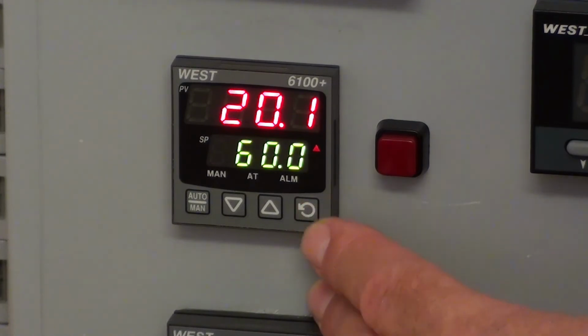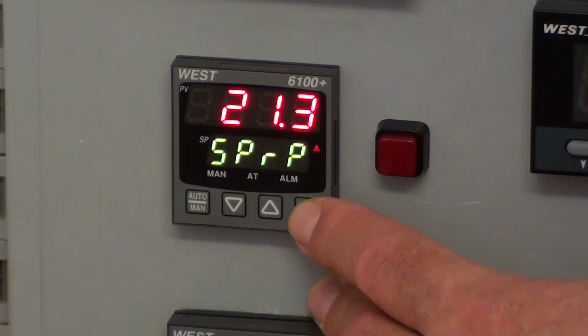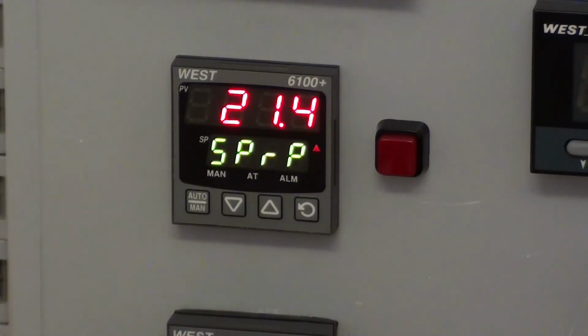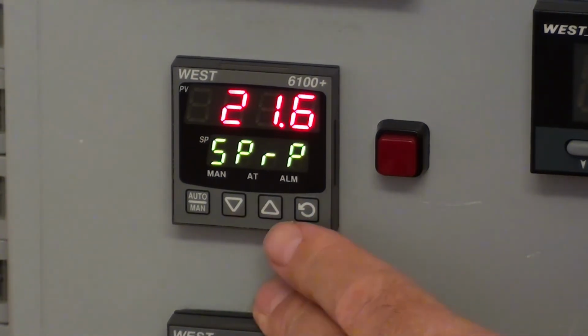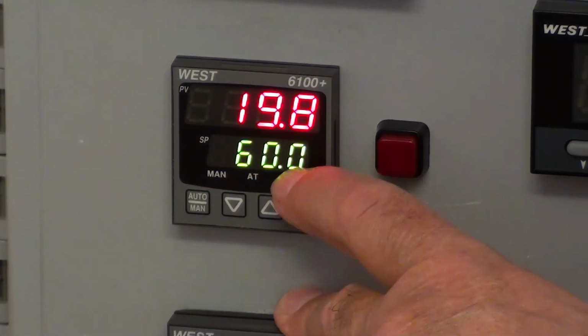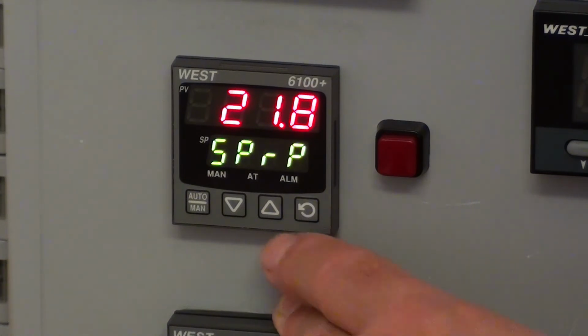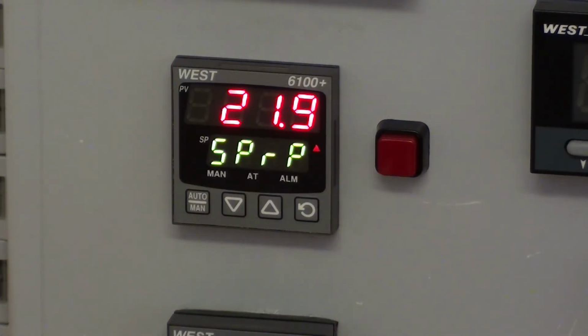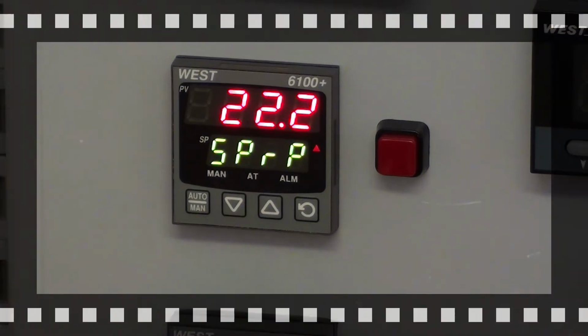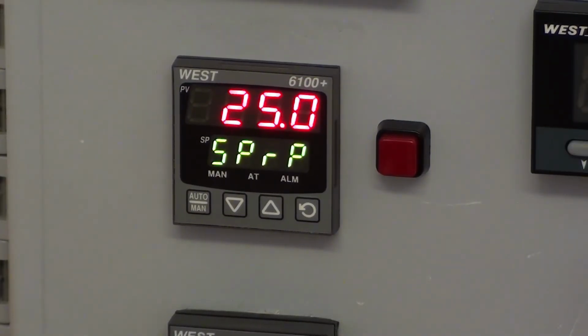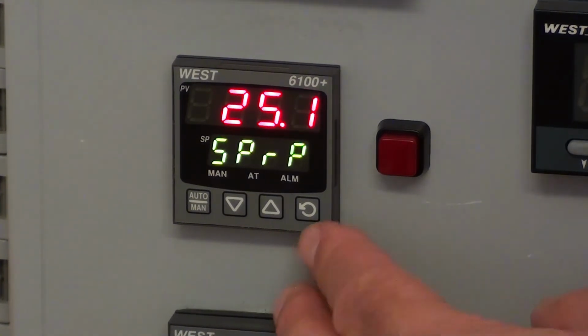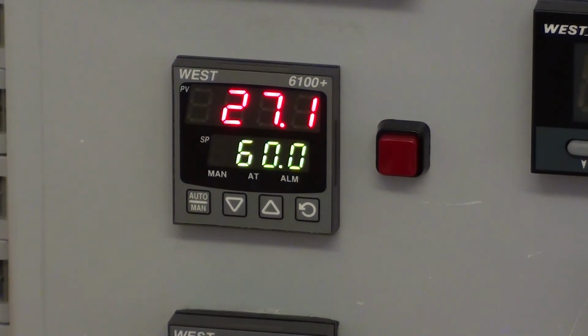If I press the scroll key, I've also enabled the feature where you can see the ramp rate on the controller. So at the moment it's showing a ramping set point of 21.6. The target set point is 60, but at the moment the ramping set point that the controller is working towards is just 22 degrees and it's going up at 2 degrees per minute. The ramping set point at the moment is 25.0 and the process temperature is 27.2. We'll come back in a few minutes to see how it's getting on.